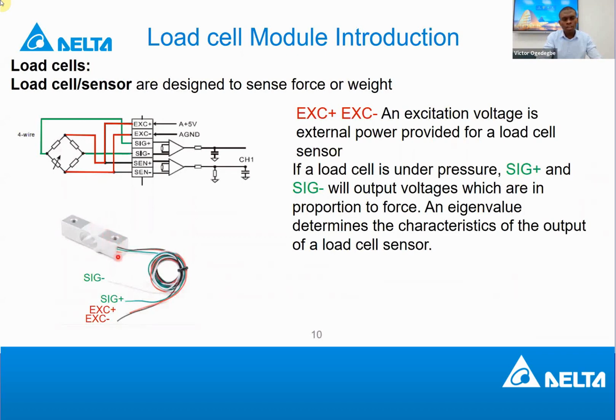For this to work efficiently, the load cell has this internal configuration. It receives what we call the excitation voltage. This is the plus, this is the minus. The load cell module, like we saw on the first page, supplies this excitation voltage to the load cell. This is the strain gauge, the cell itself. If a force is applied here, there will be a change in electrical resistance, so there will be a signal corresponding to the applied force. That force will generate a very small voltage, in millivolts, corresponding to the force applied.